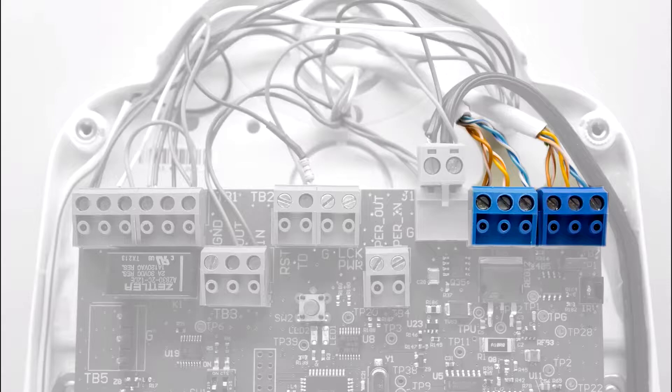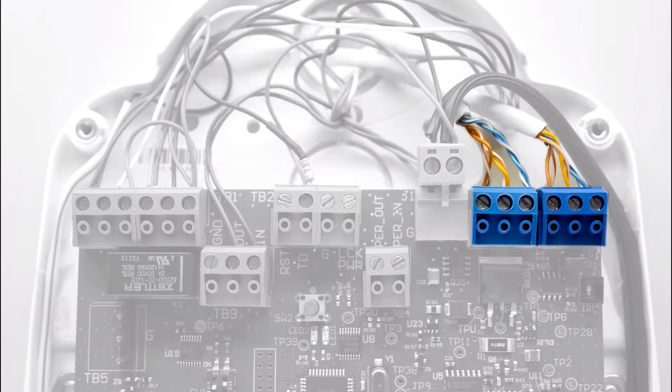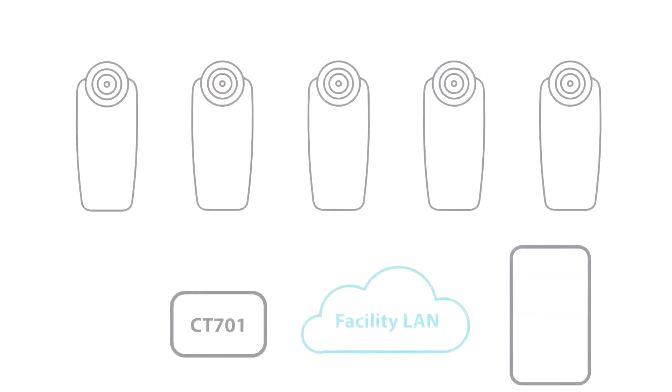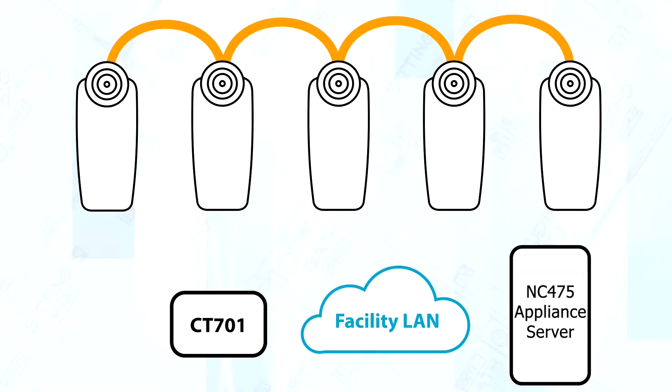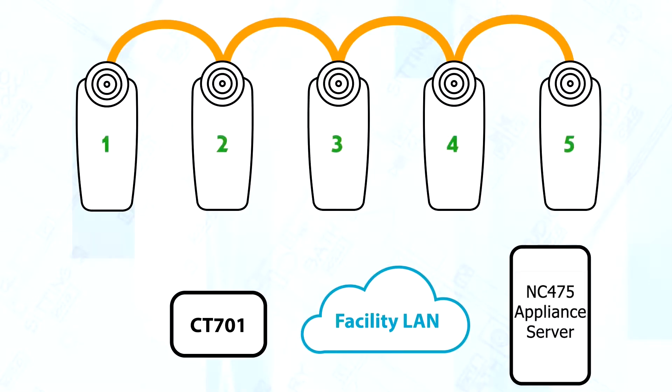These terminals are used to connect door controllers and display units together on the network. Each door controller must be assigned a unique address to communicate on the TechCare 700 network. When the door controllers are shipped, they are all assigned to address 30.